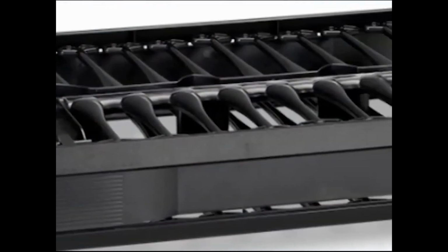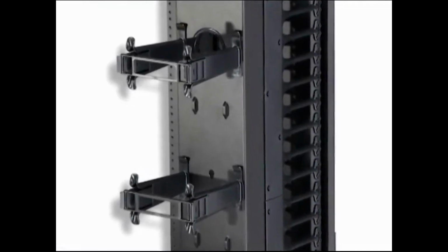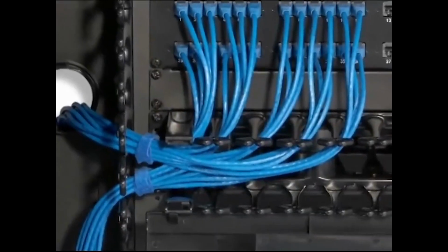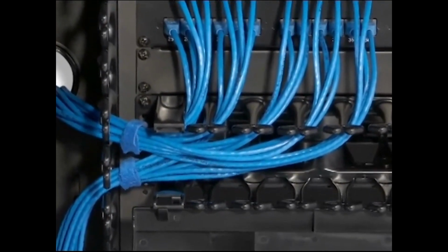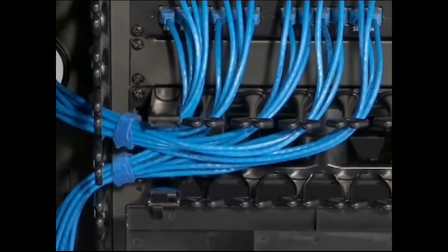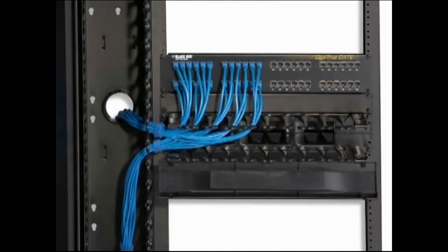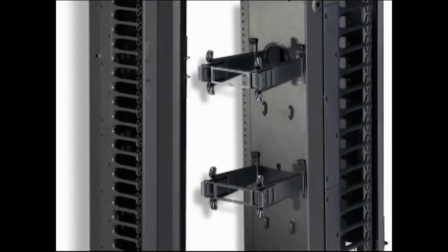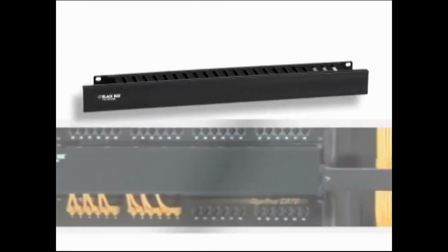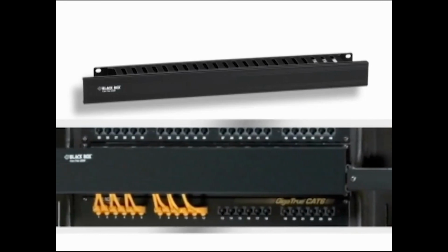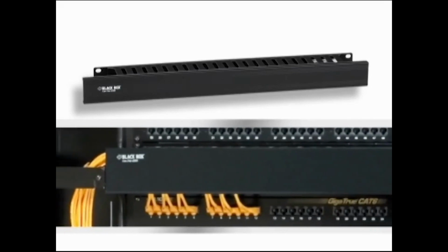Finally, for high-density applications, there are specially designed cable managers that handle large amounts of cables. These complete systems have oversized channels with molded fingers that guide wiring to mounted devices at precise increments while maintaining the proper bend radius for the cable. They also have covers that you can remove completely for faster cable installation. And while vertical managers are great for organizing cable runs top to bottom in a rack, horizontal managers are designed to guide cables and hold them precisely at the same level as mounted equipment. They're also designed for easy front-to-back pass-through.